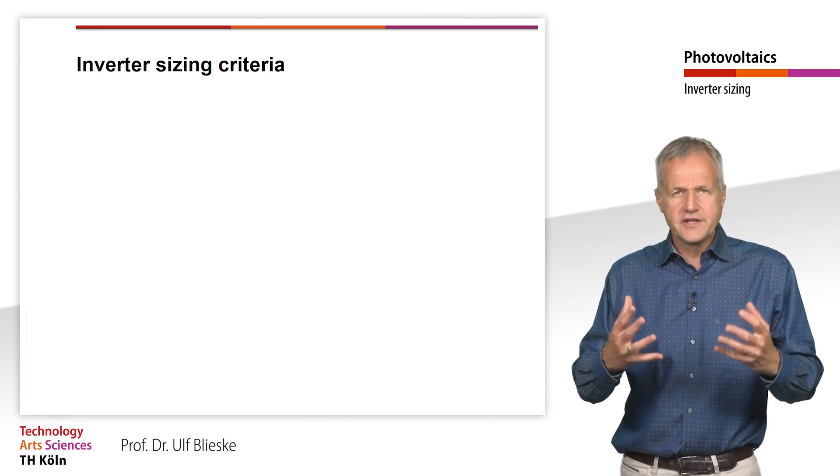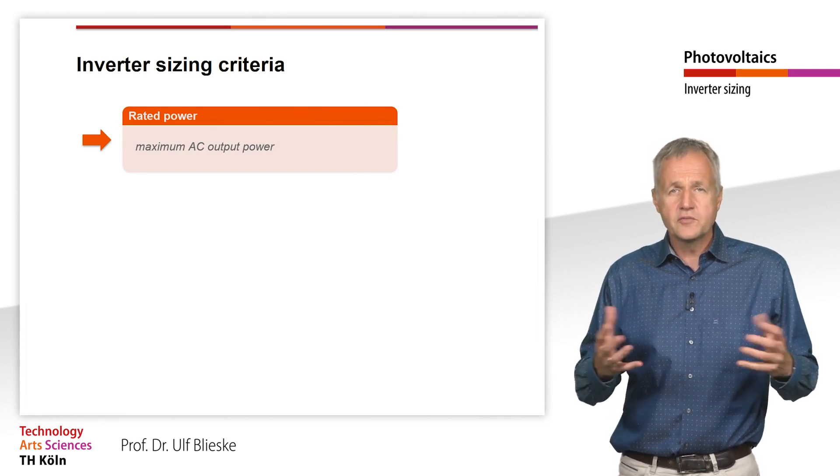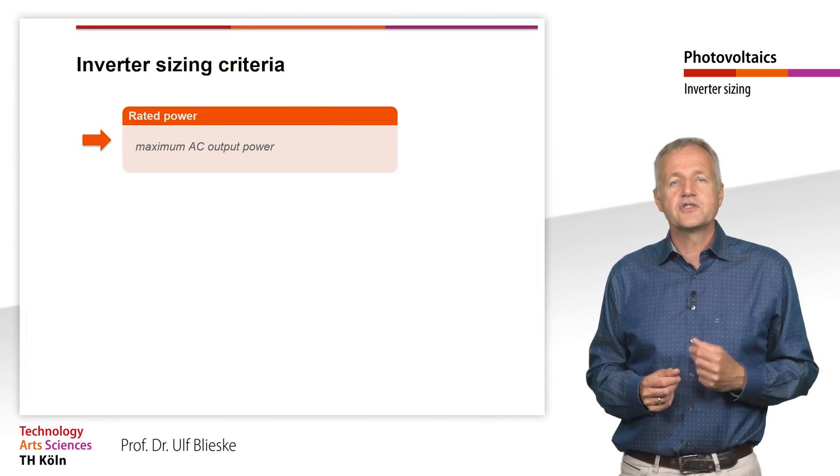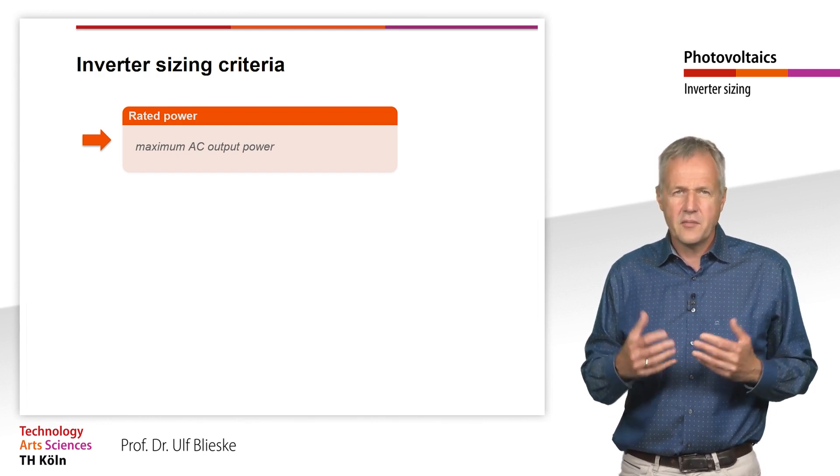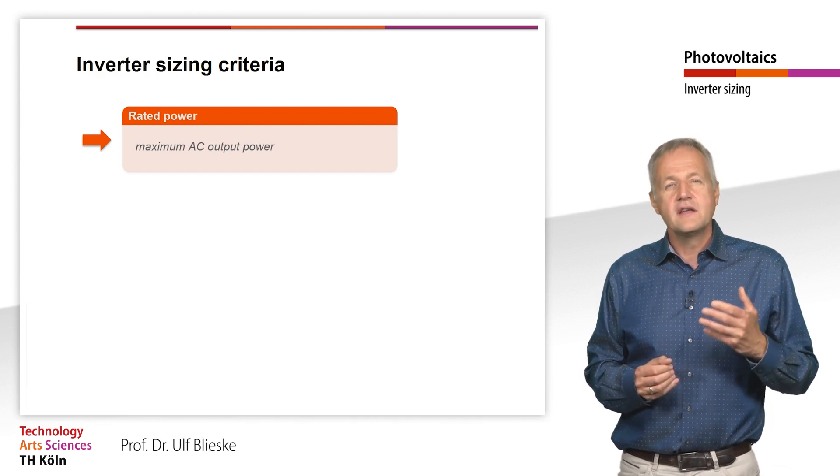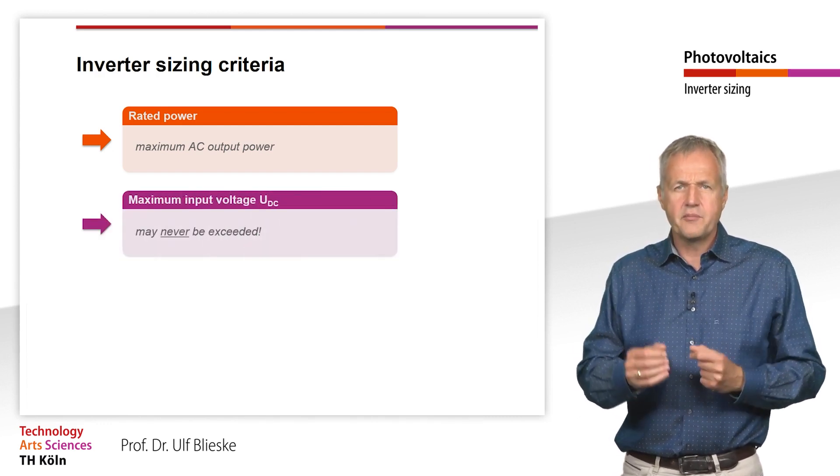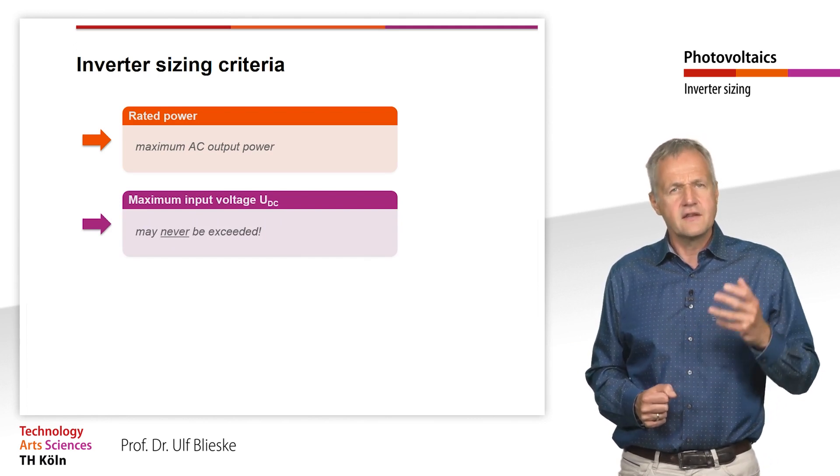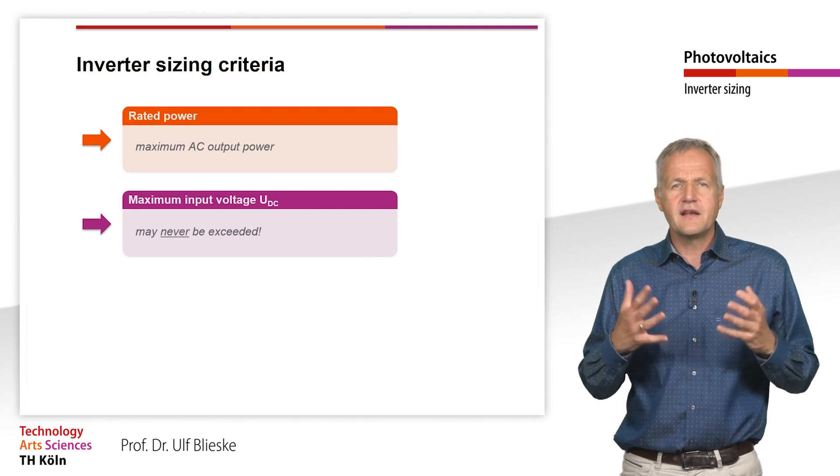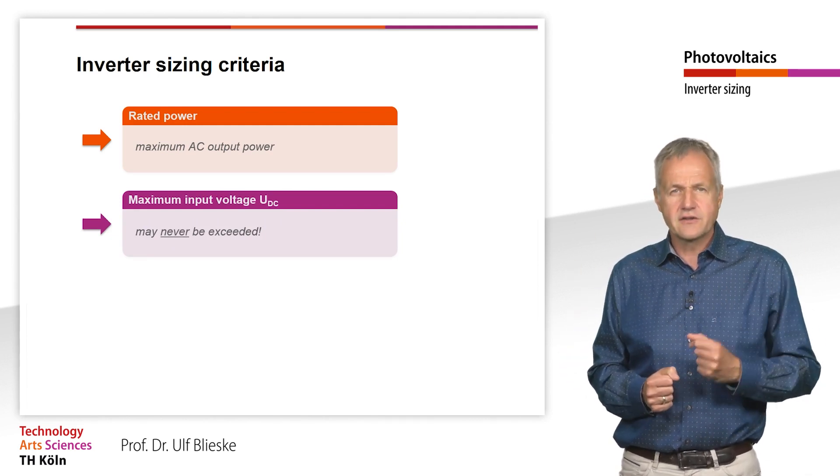First of all, an inverter has a certain rated power. This corresponds to the maximum AC output power that the inverter can deliver. Next, an inverter has a maximum permissible input DC voltage, which must never be exceeded when the system is in operation.